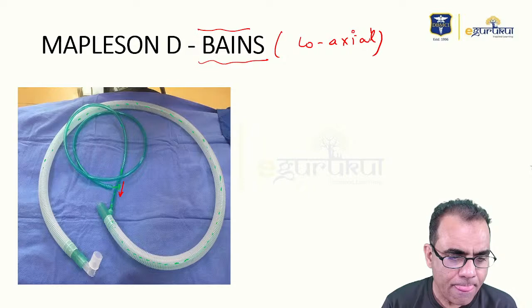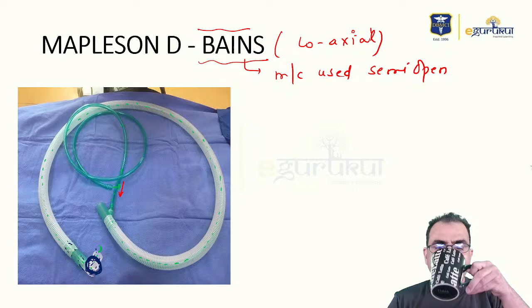Expiratory gases go through the outer tube. So there is no mixing in between. The only mixing point is this small point where the fresh gas tube ends. This is the only point where there is a possibility of mixing. So the mixing possibility is drastically reduced. That means this Bain circuit becomes very effective, and so you can say that the Bain is the most commonly used semi-open circuit.